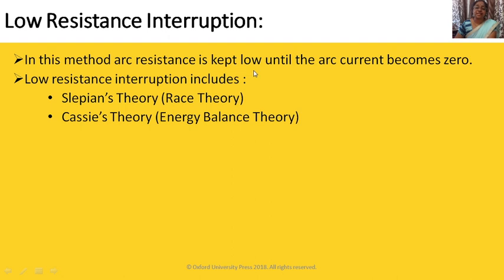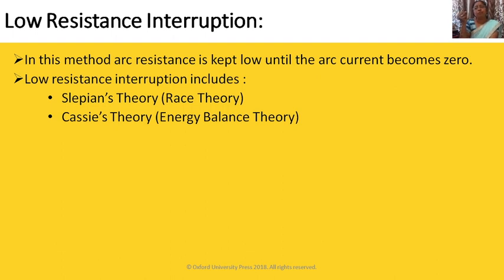In the low resistance interruption method, arc resistance is kept low until the arc current becomes zero. This method is applicable for AC circuits because AC has an alternating waveform — it passes through zero. When current becomes zero, the arc is quenched for a brief moment. It passes zero twice in a cycle. This is called the low resistance interruption method and is applicable only for AC circuit breakers.